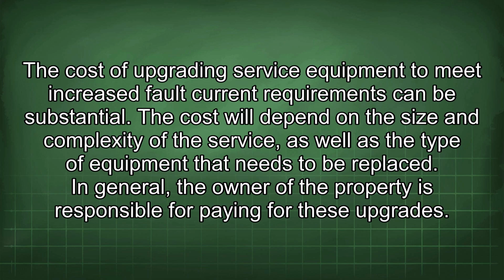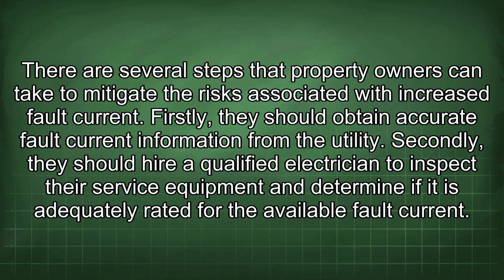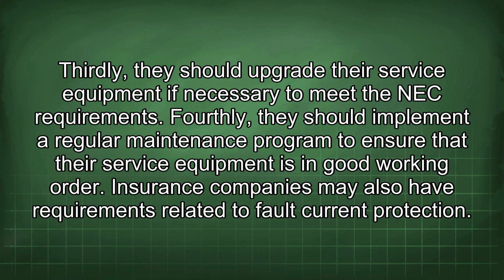The cost will depend on the size and complexity of the service, as well as the type of equipment that needs to be replaced. In general, the owner of the property is responsible for paying for these upgrades. There are several steps that property owners can take to mitigate the risks associated with increased fault current. Firstly, they should obtain accurate fault current information from the utility. Secondly, they should hire a qualified electrician to inspect their service equipment and determine if it is adequately rated for the available fault current. Thirdly, they should upgrade their service equipment if necessary to meet the NEC requirements. Fourthly, they should implement a regular maintenance program to ensure that their service equipment is in good working order.